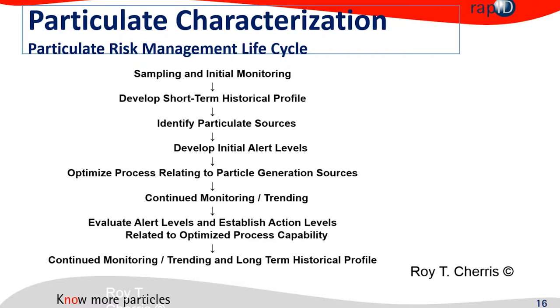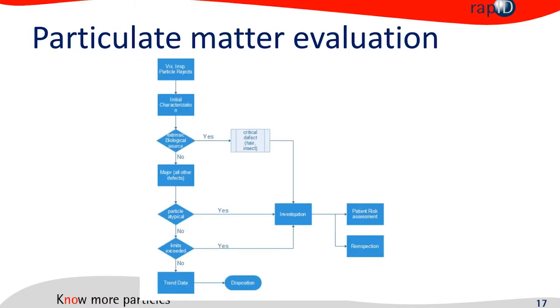This slide from Roy shows that when you look into the 'shoe box of rejects' during sampling and initial monitoring, you can develop a short-term historical profile — you have different categories of particles that you find and start identifying their sources. Then you can develop initial alert levels and optimize the process, going on with monitoring and trending. After evaluating and establishing alert levels, you can set action levels that trigger action in certain critical quality aspects.